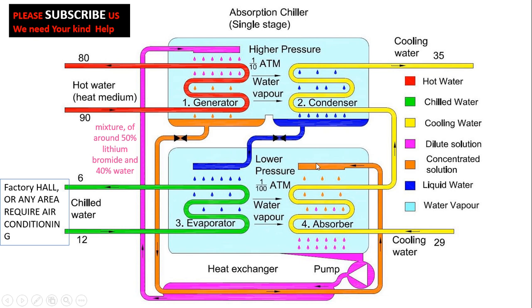The output of the absorption chiller is cooling and air conditioning of a factory hall or any area requiring conditioning. We get a cold water line from the absorption chiller — for example, water enters the production hall at 6°C and returns to the chiller at 12°C.